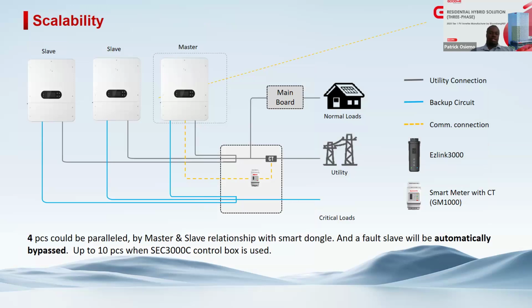Scalability is also a very notable feature in residential houses, with houses also increasing in terms of occupancies, in terms of electrical loads and the likes, or even inductive loads. The ETLV has optional ways in which you can scale up your system. There are two options. If you're scaling up your system between 1 to 4 pieces, then you can easily use the special communication dongle called the Ezlink3000. And if you're doing more than 4 pieces, let's say between 5 to 10 pieces, then you have the option of connecting the SEC 3000C, which is our control box. Now, the SEC 3000C allows you to connect up to 10 pieces, while the Ezlink3000 allows you to scale up to 4 pieces.